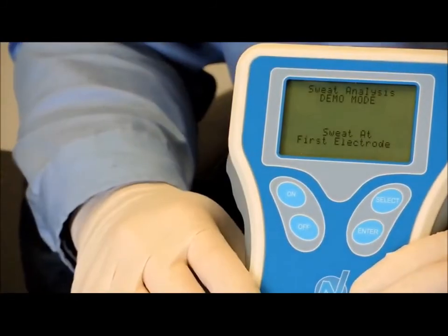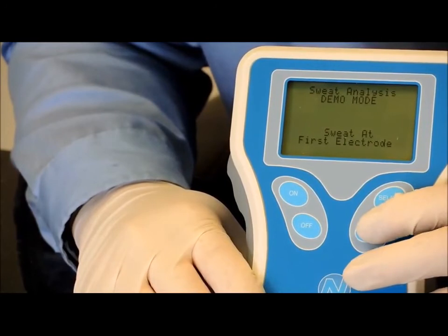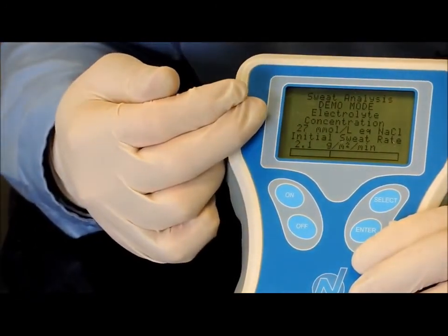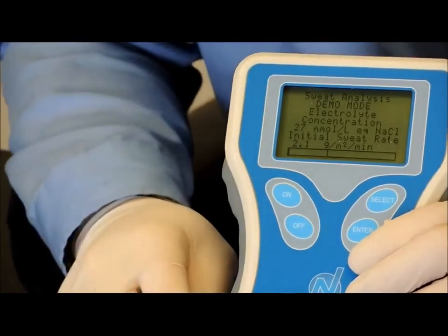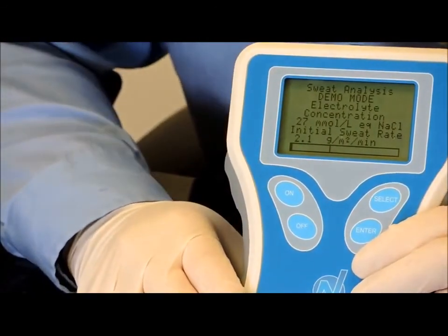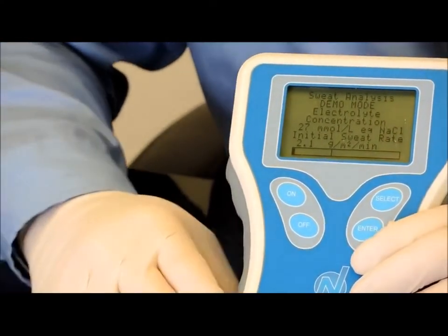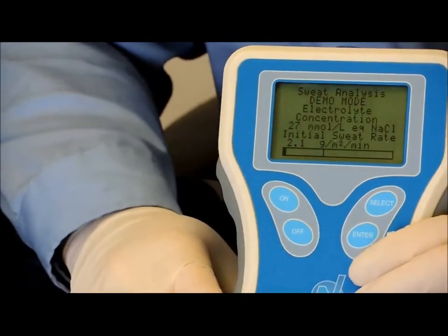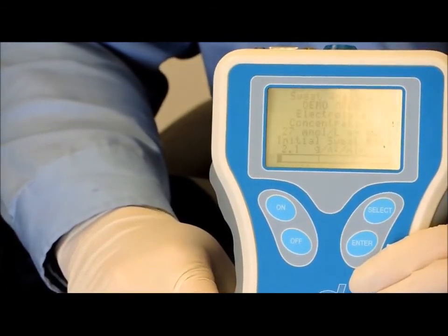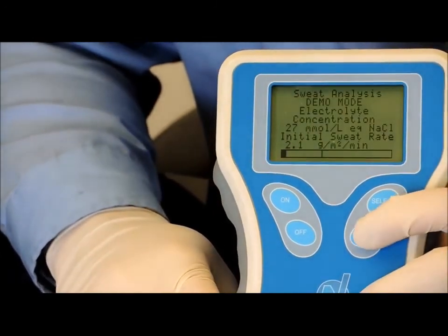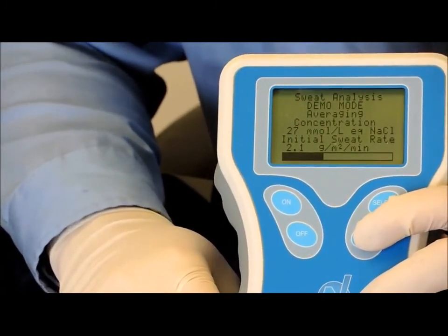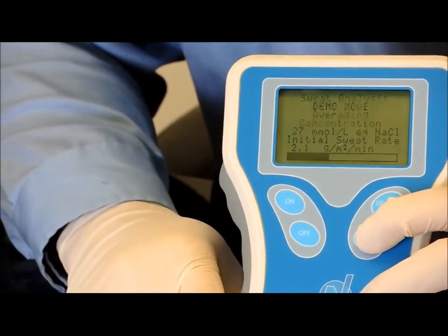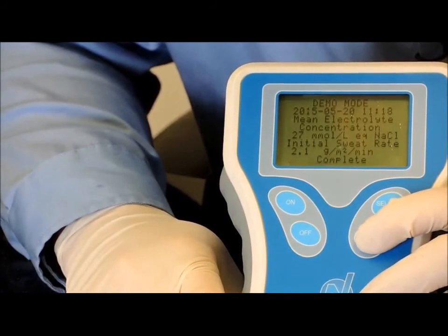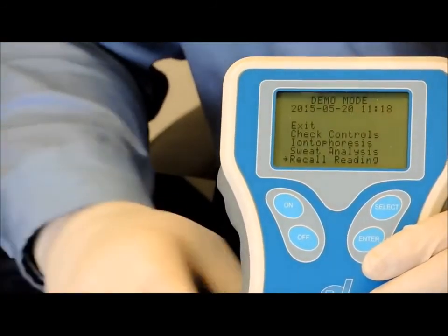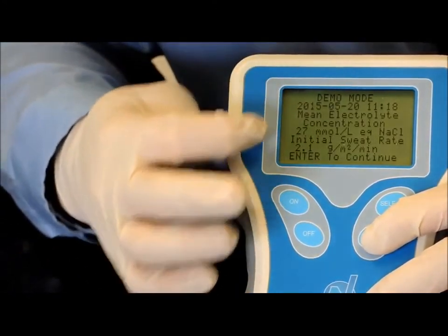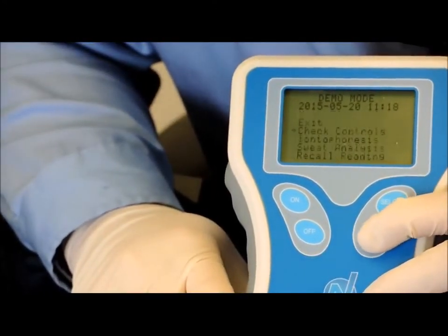Now you see sweat at first electrode. I'll press enter again, and now it's showing a value of 27 and a sweat rate of 2.1. Again, those are just random values that appear as you're showing this to a customer, and it has a progress bar, the 8-minute progress bar, like you normally would expect if you were actually collecting sweat. And you can just continue to hit enter, and it automatically progresses through the next step all the way to completion. And when you're complete, just like a normal test, you can recall the reading and see what the reading was.